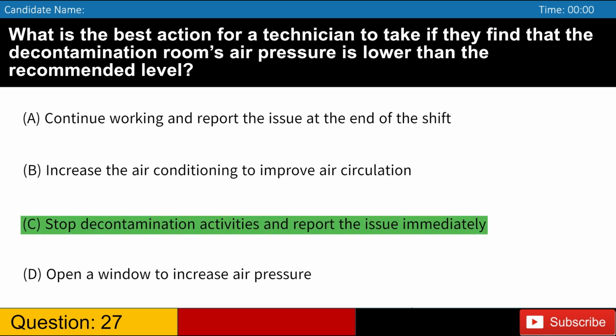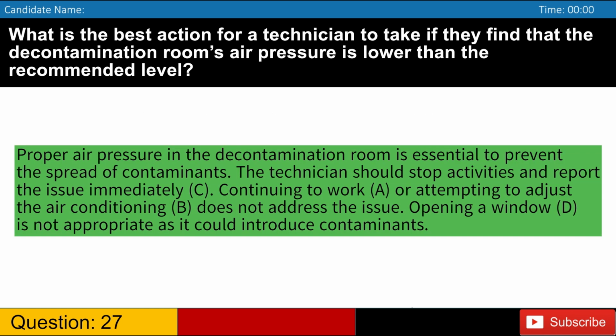Answer, C. Proper air pressure in the decontamination room is essential to prevent the spread of contaminants. The technician should stop activities and report the issue immediately, C. Continuing to work, A, or attempting to adjust the air conditioning, B, does not address the issue. Opening a window, D, is not appropriate as it could introduce contaminants.